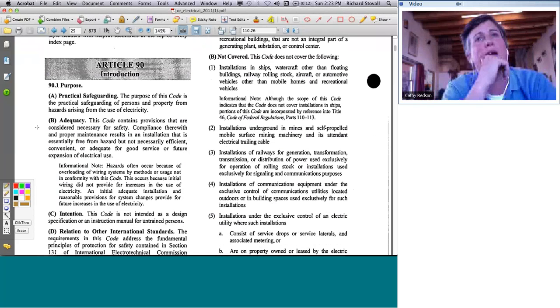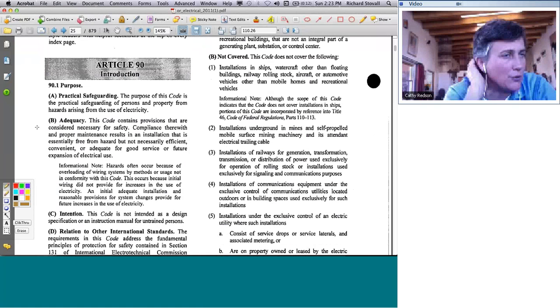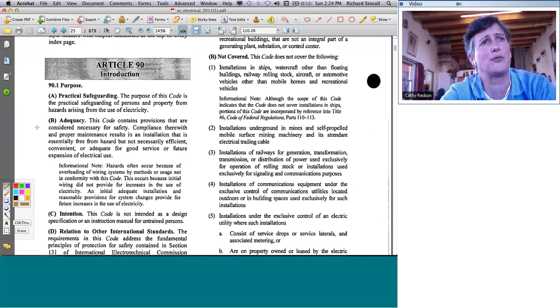I was trying to figure out how we were going to do that and needed to contact them to see if they minded if I made an attachment penetrating the back of the unit into the actual encasement. Of course, they said that would void the warranty, but I said, you know, in the 2011 code, you don't have to have a separate grounding electrode conductor coming out of the inverter. So the Sunny Boy 700 is code compliant with the two connections in the grounding lug that it has, the way the 2011 code is, but it's not code compliant for the 2008 code without adding a separate bonded grounding lug that has the ability for you to attach more than two attachments.